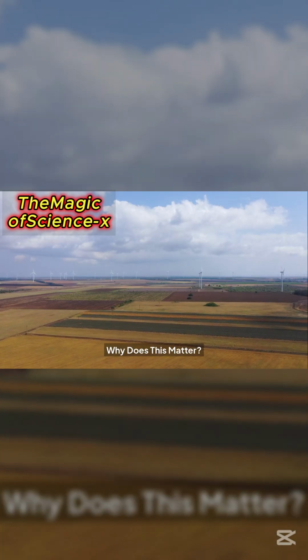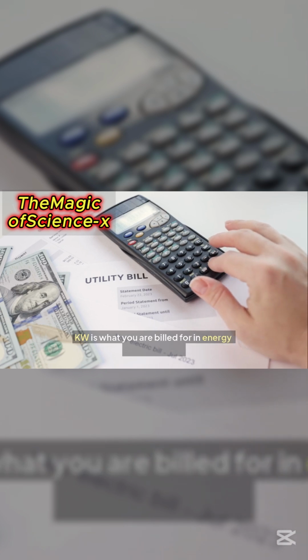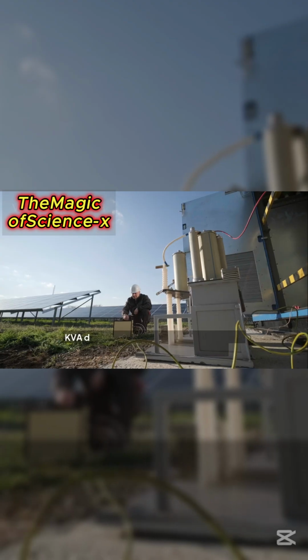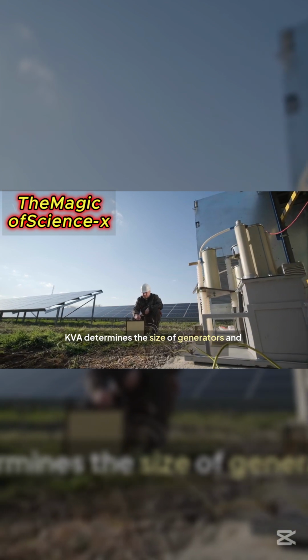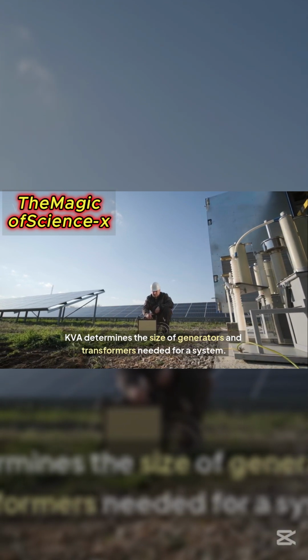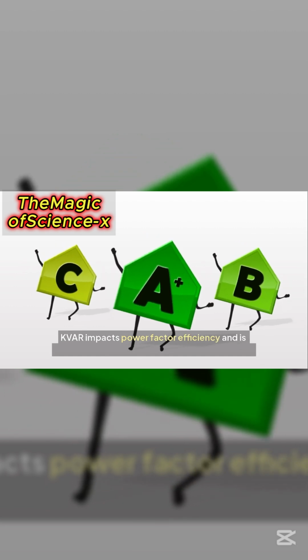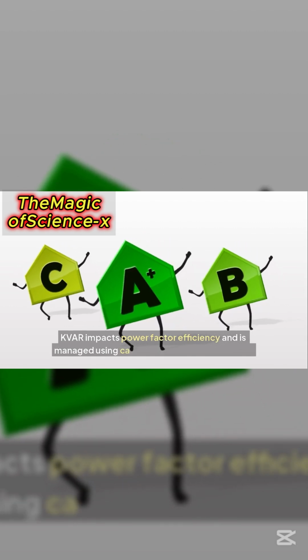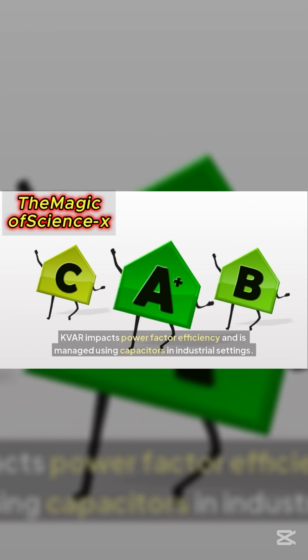Why does this matter? KW is what you are billed for in energy consumption. KVA determines the size of generators and transformers needed for a system. KVAR impacts power factor efficiency and is managed using capacitors in industrial settings.